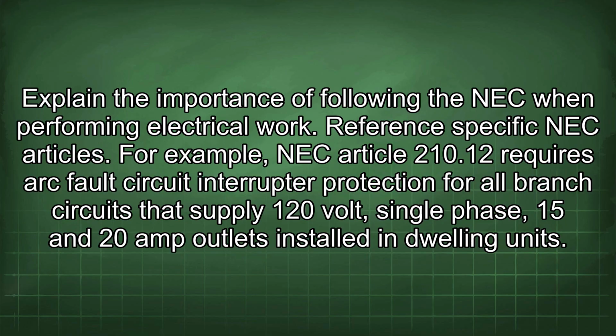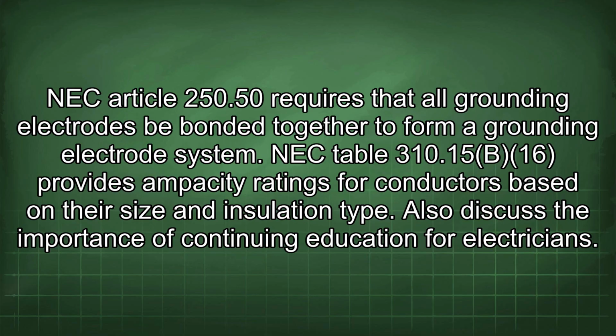Reference specific NEC articles. For example, NEC Article 210.12 requires arc fault circuit interrupter protection for all branch circuits that supply 120-volt, single-phase, 15 and 20 amp outlets installed in dwelling units. NEC Article 250.50 requires that all grounding electrodes be bonded together to form a grounding electrode system. NEC Table 310.15(B)(16) provides ampacity ratings for conductors based on their size and insulation type.